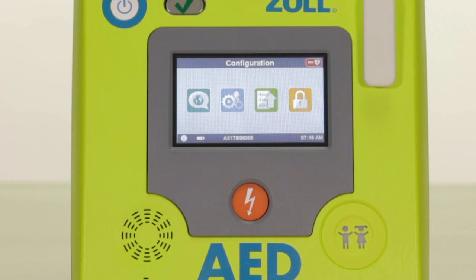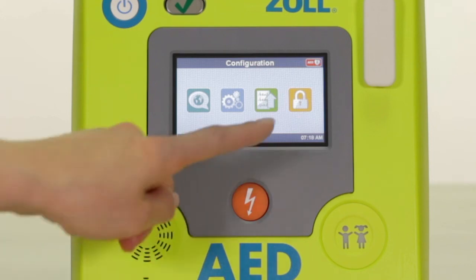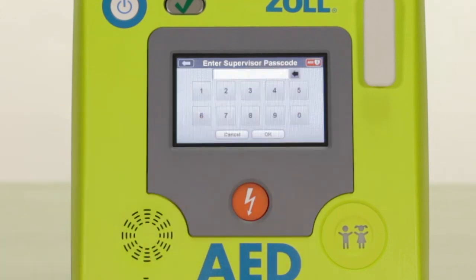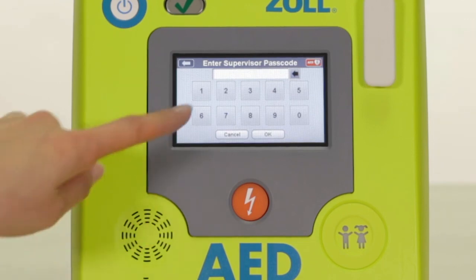The last icon on this screen is the locking feature that allows only authorized users to access the advanced configuration features of the AED. Press the yellow lock icon and enter the passcode. The default passcode on a new AED 3 is 123456.